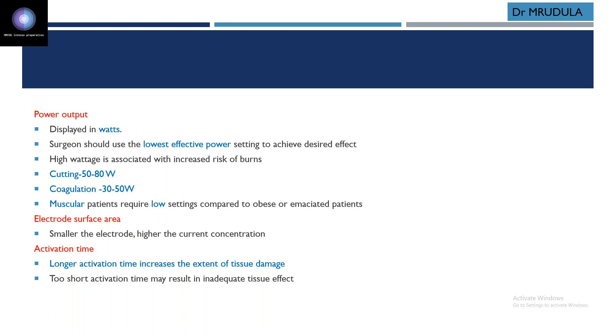Electrode surface area: the smaller the electrode, the higher the current concentration. Activation time: the longer the activation time, the greater the extent of tissue damage. Too short an activation time may result in an inadequate effect. This is again what I have given with the waveforms. The same thing is repeated in this table, showing exactly what happens with different temperatures and different effects.